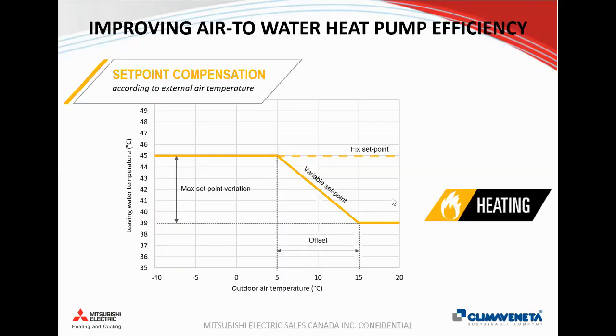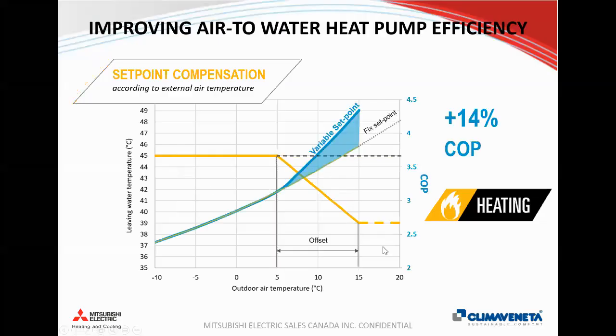Just one other note, in boilers, we use outdoor reset. You can do the same thing with heat pumps as well, following the heat loss curve for the building. You can program in fixed curves within the heat pumps to automatically change your supply temperature according to outside air temperature to enhance energy savings. So in this example here, just by having a curve implemented from 45 degrees, dropping your supply temperature to 39 degrees, from 5 to 15 outside air temperature, you can increase the COP from the heat pump as you do that. So there are ways that you can still implement the technology and further enhance the operation of it instead of a fixed supply temperature at all times.